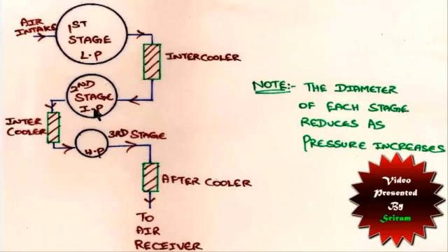And if you keep the intermediate stage at the same diameter as the first stage, all the compression and the work input to compress and increase the pressure of air would be lost, and then it will expand again. And it is for this reason there is always a convergence, a steep decrease in the size of the cylinders as the pressure stages increase.